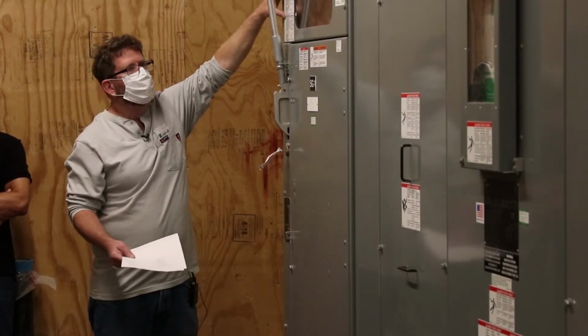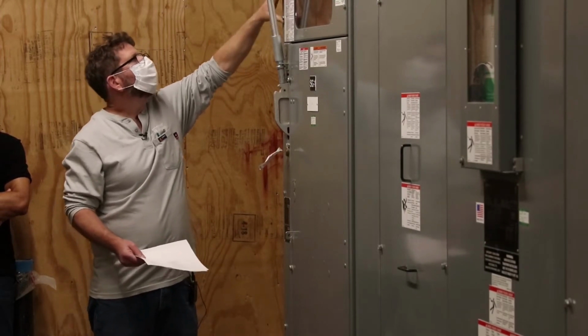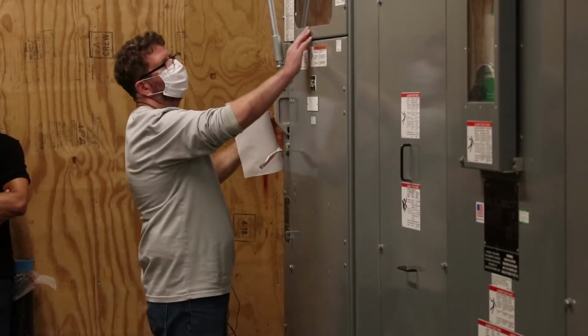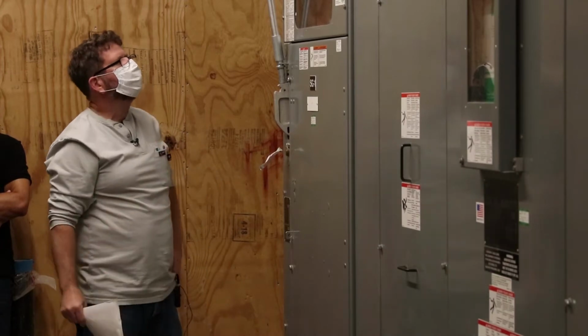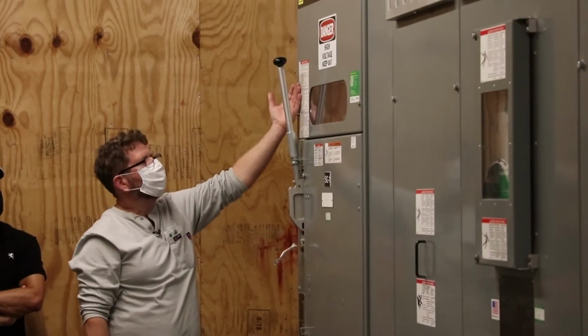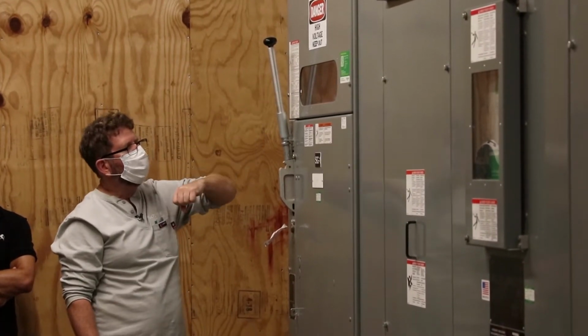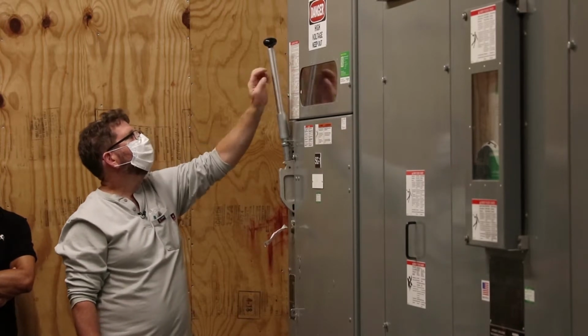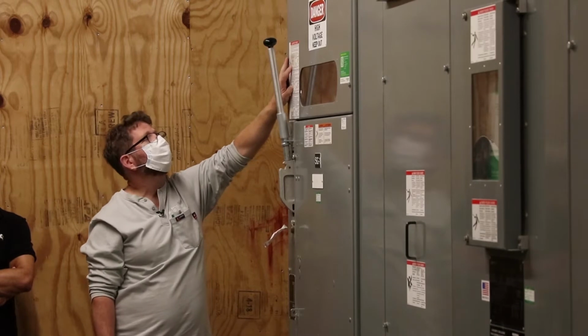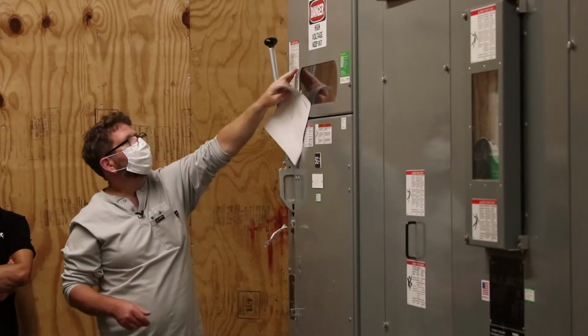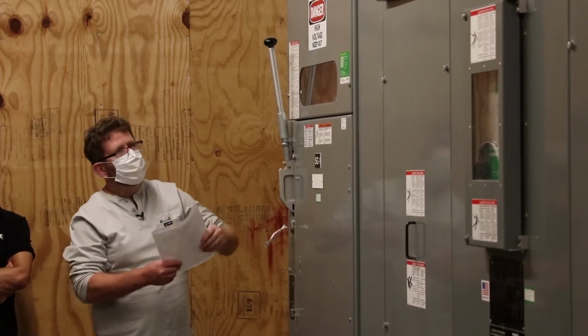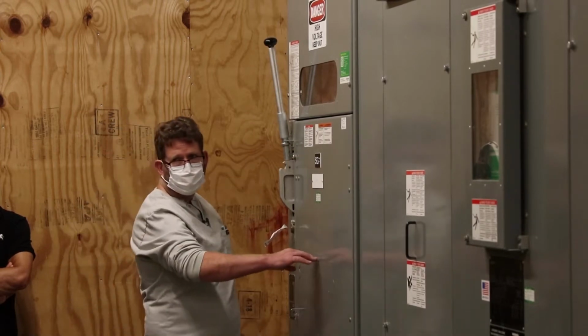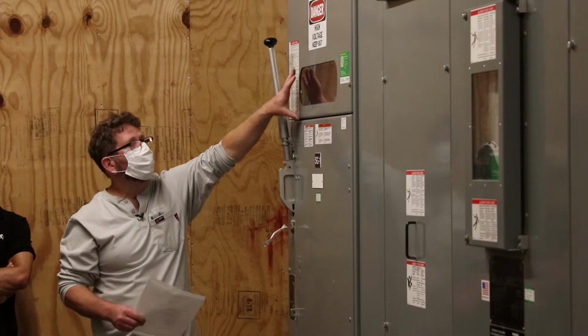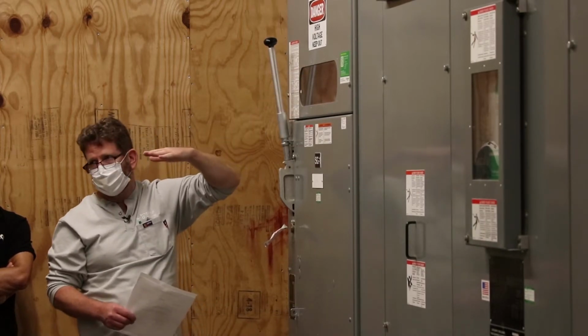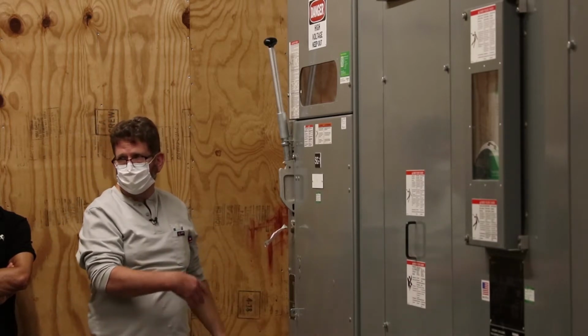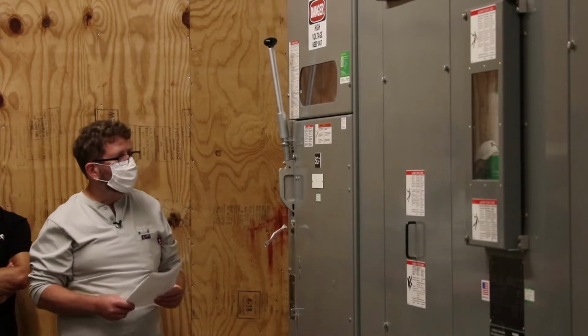You'll see all electrical equipment has all kinds of danger labels. This one's no exception. When you operate this switch, you can look in through the window to see the switch contacts. And this is telling you that the switch blades can stick in. So you open the switch, you think it's open. I don't know if you can see that or not, but this is showing the switch blades open. This is showing the arc tips still stuck in the arc chute. If the arc tips are stuck in the arc chute with the handle open, that means all this is now still live. So when you open the switch, you want to look in through the window and verify the blades are all open, and obviously if you're going to do work in there, that's when you would want to check it de-energized with a properly rated voltage tester.